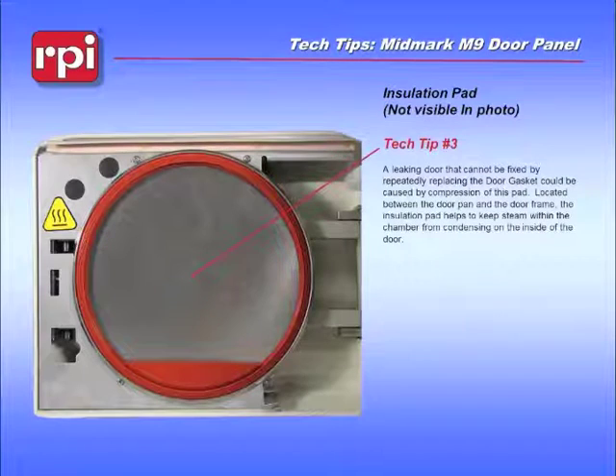Behind this metal plate, there is a piece of insulation that keeps the door from becoming a heat sink. That piece of insulation gets pressed when you shut the door, and in some situations can become unevenly pressed. One side gets pressed in a little bit more than the other side, and that can cause door leaks. So if you have a door leak that isn't solved by replacing the door gasket, you might want to consider replacing the insulation pad.